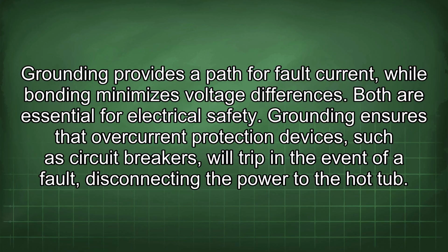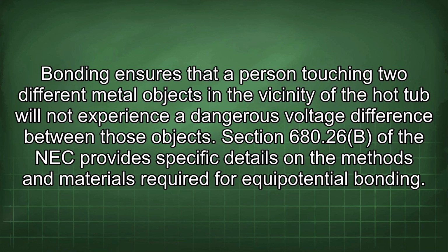Grounding ensures that overcurrent protection devices, such as circuit breakers, will trip in the event of a fault, disconnecting the power to the hot tub. Bonding ensures that a person touching 2 different metal objects in the vicinity of the hot tub will not experience a dangerous voltage difference between those objects.